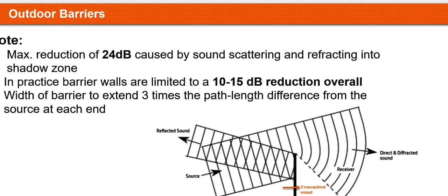For practical purposes, the maximum performance in one shot, single number rating average that you could get from a barrier wall is going to be 10 to 15 decibels. So how do you know you need an enclosure? It's when you need more than 10 to 15 points off your sound source to get to your 45 dBA when somebody's trying to sleep, or 35 dBA in a window of a classroom.